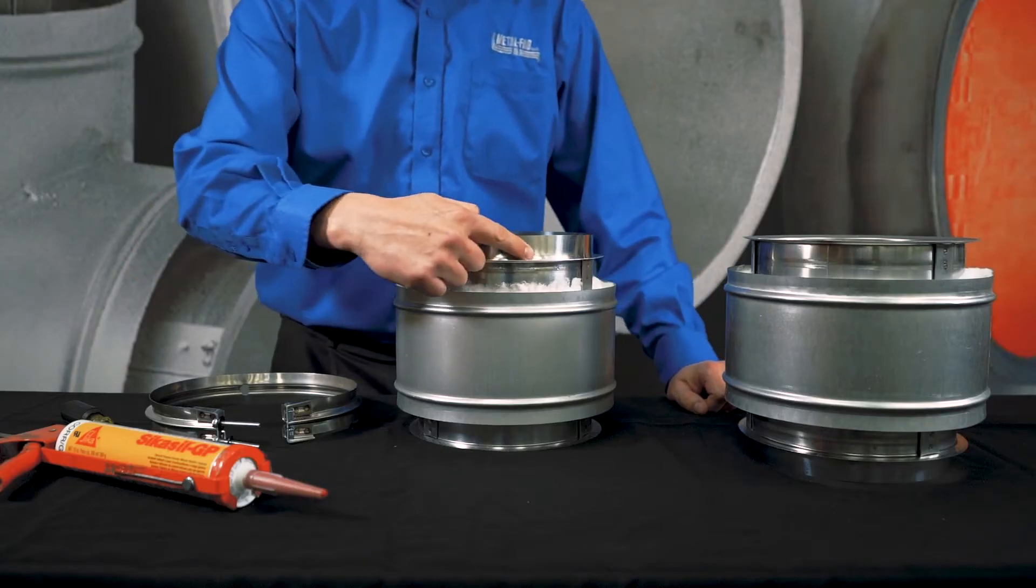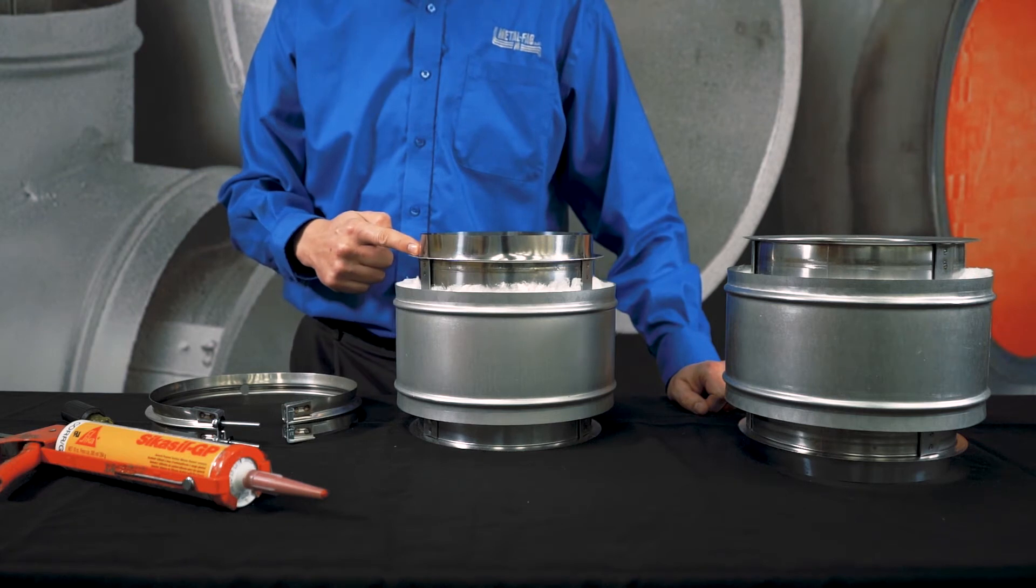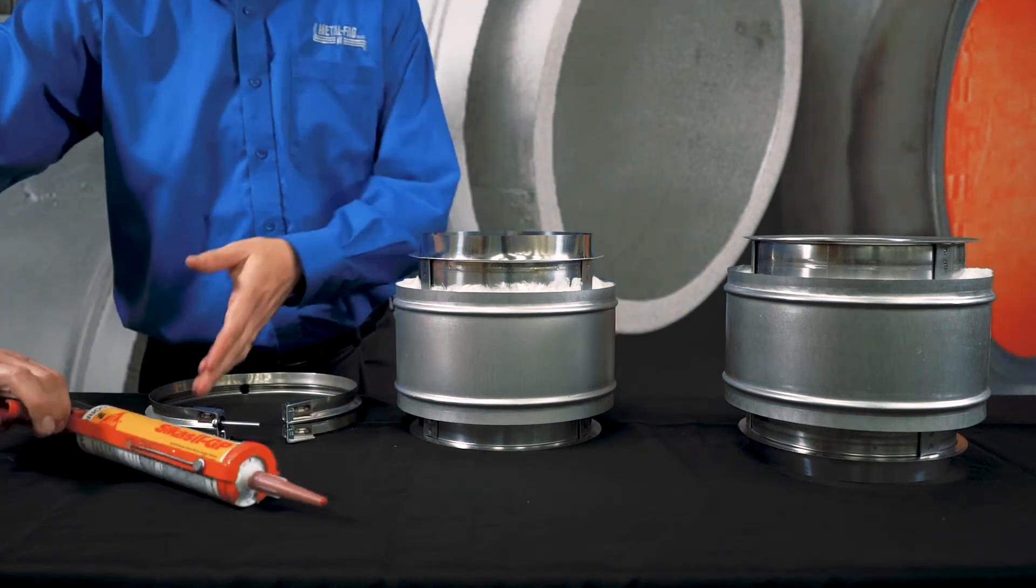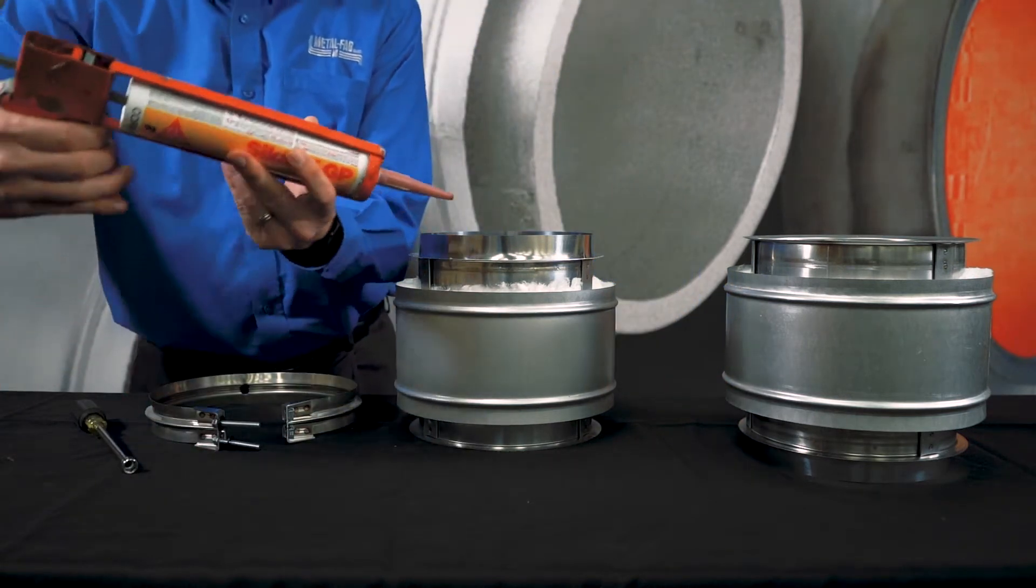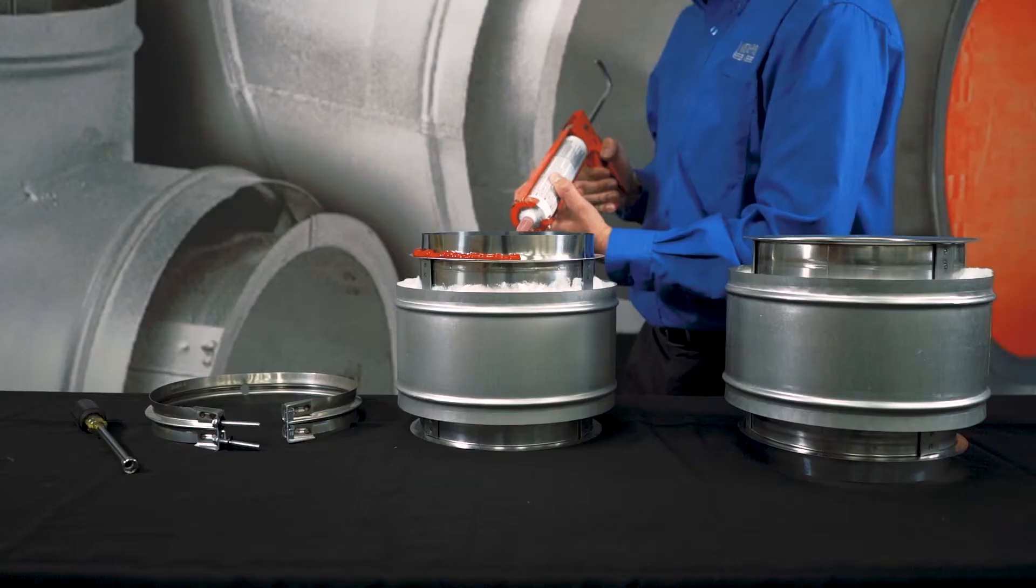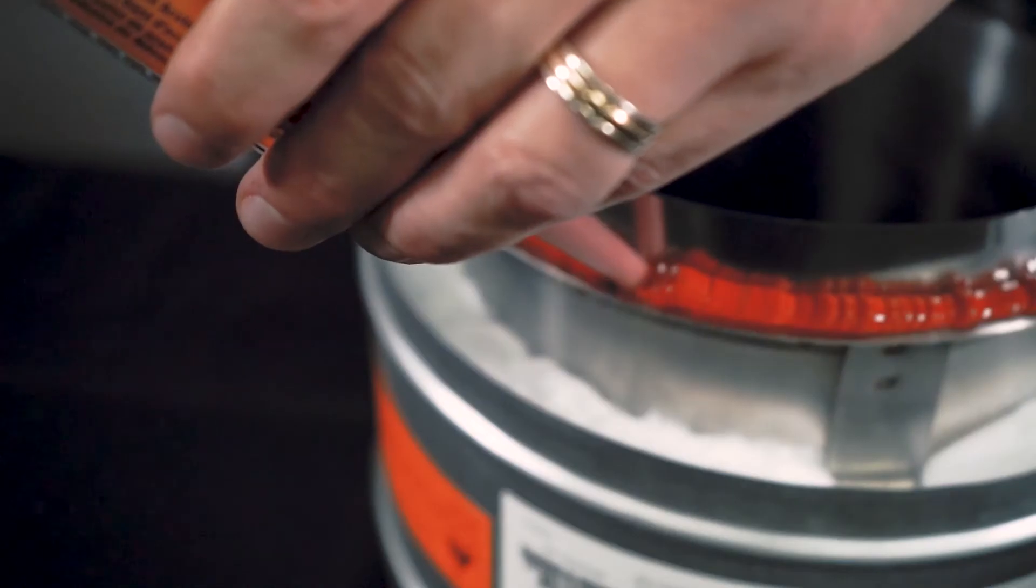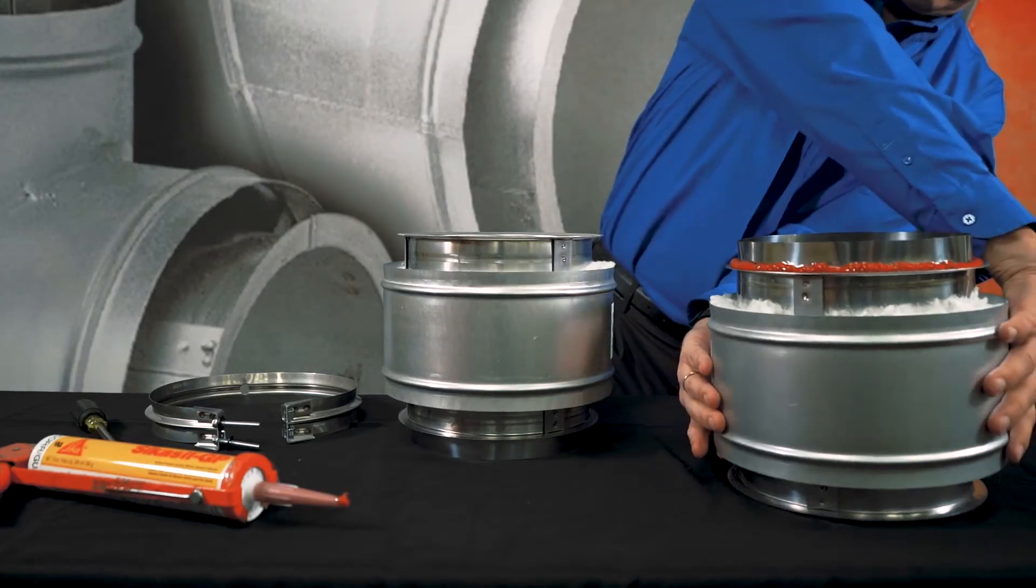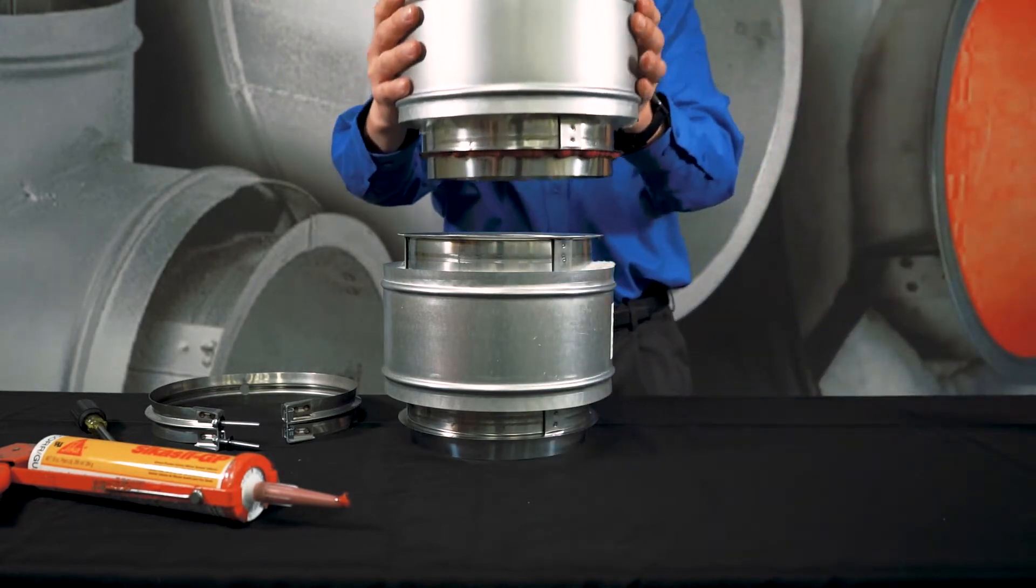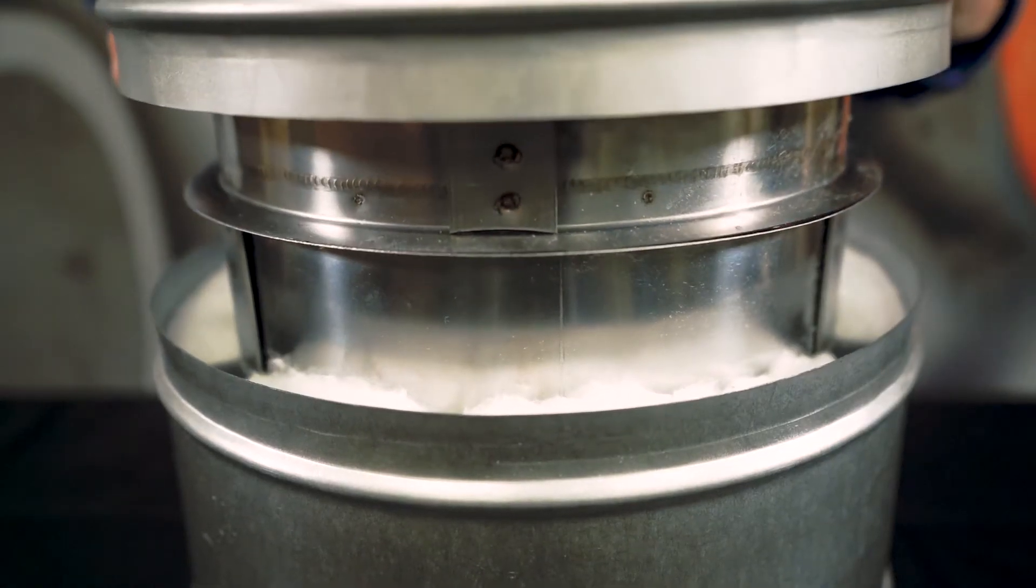Begin by inspecting the flange surfaces and cleaning with rubbing alcohol if contaminated with oil or dirt. Apply a continuous bead of the proper sealant in the corner of the sleeve and flange. Firmly join the two pieces of vent together.